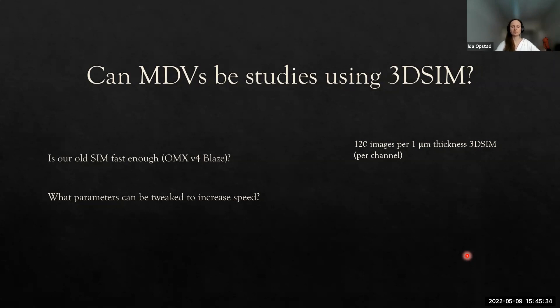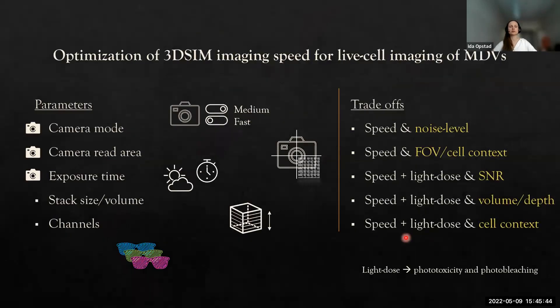I thought I'll give it a try and see what parameters can I tweak on our commercial microscope to increase the speed. What I found most significant was to change the camera mode.